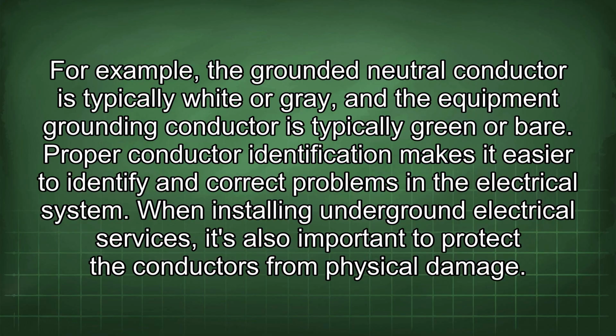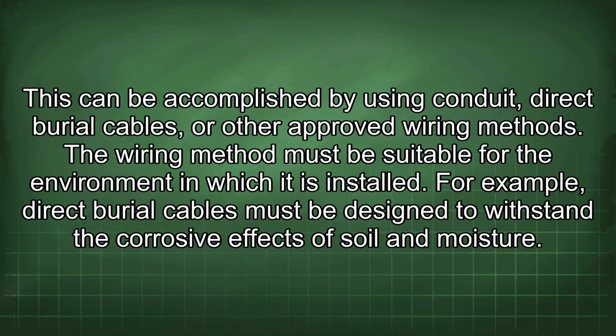When installing underground electrical services, it's also important to protect the conductors from physical damage. This can be accomplished by using conduit, direct burial cables, or other approved wiring methods. The wiring method must be suitable for the environment in which it is installed. For example, direct burial cables must be designed to withstand the corrosive effects of soil and moisture.